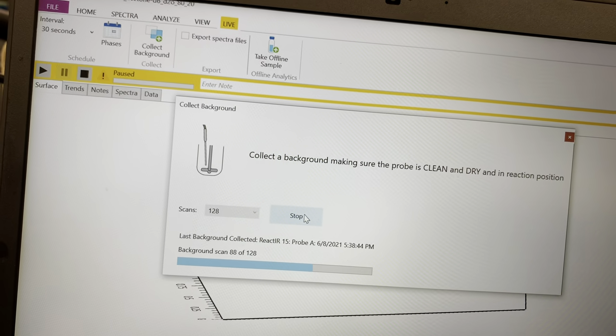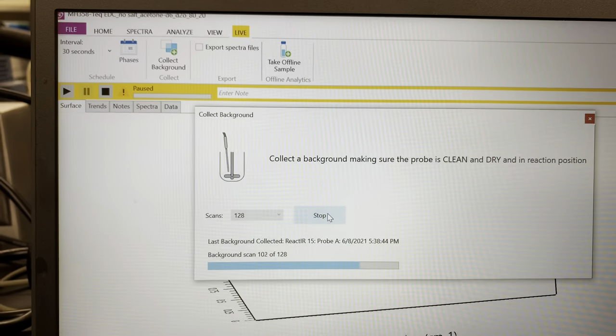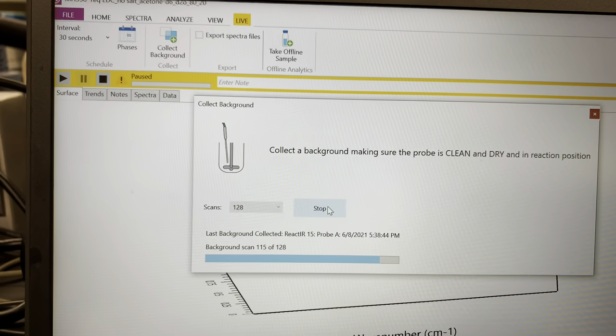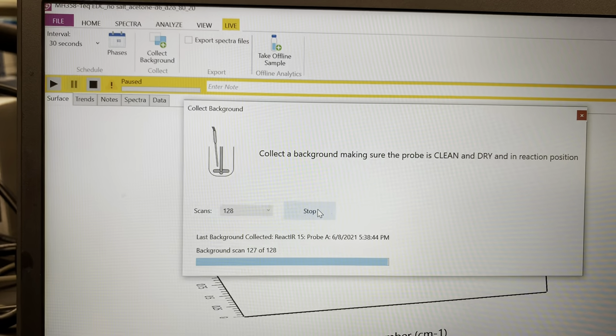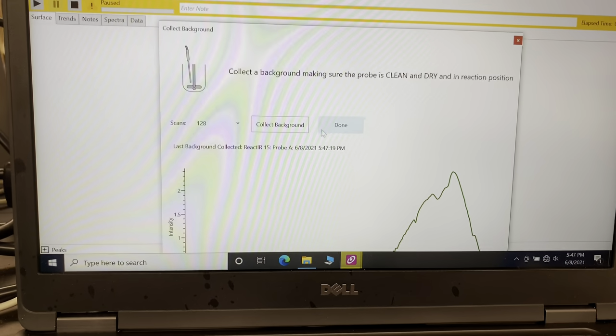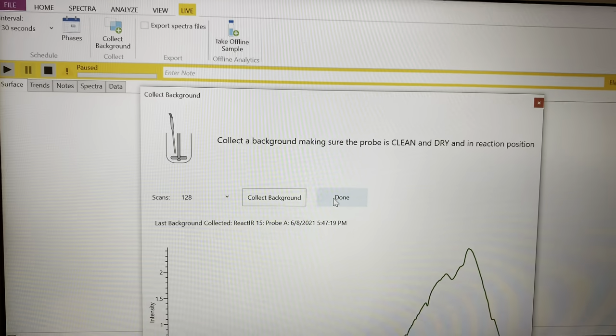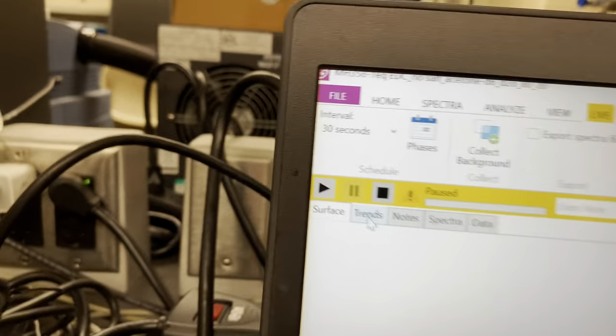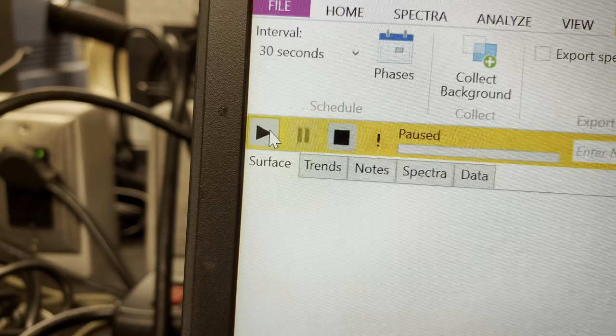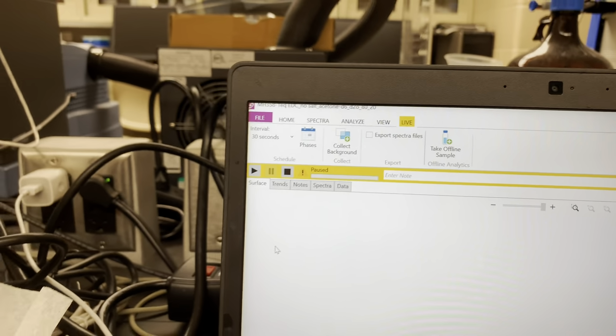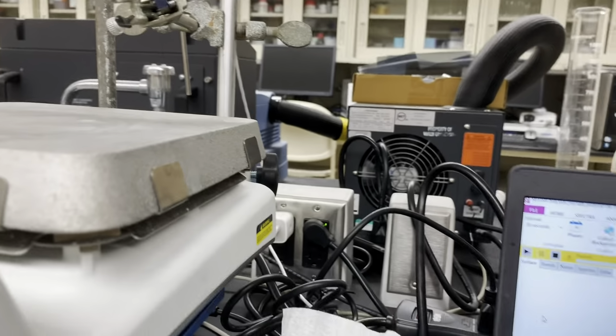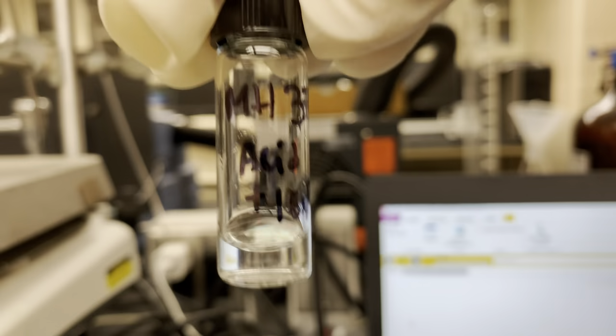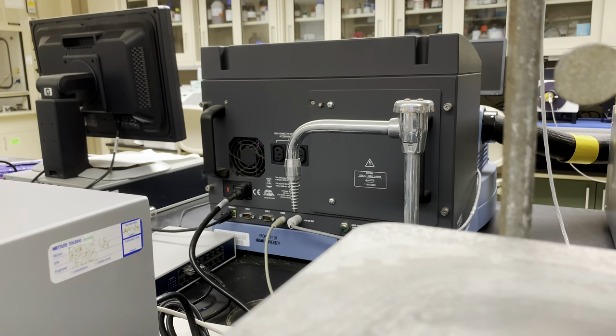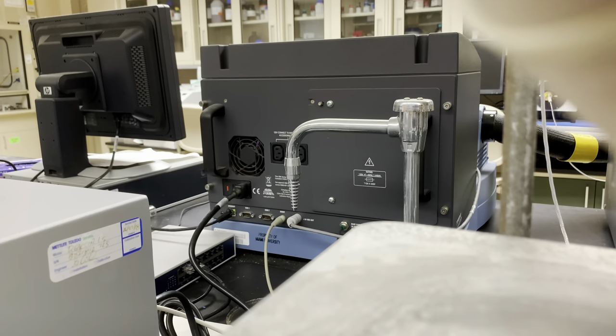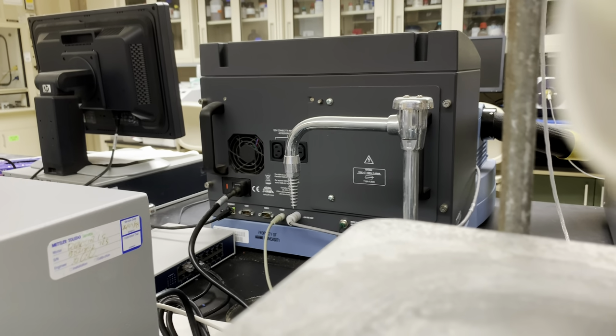So you can add one reagent in a vial and immerse it with the probe, and then before adding the second reagent, you can start that triangle button. Even if you start earlier than the addition of the second reagent, it's fine, because if it is not reacting, it will be at a certain baseline. So you'll see in the original experiment trend when I show you the reaction trend.